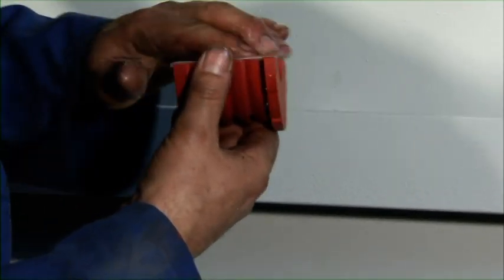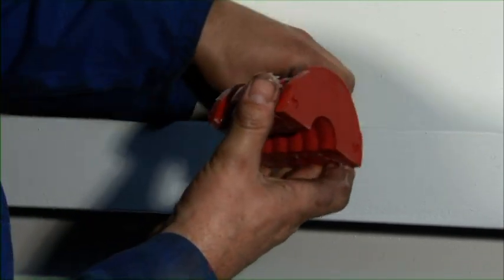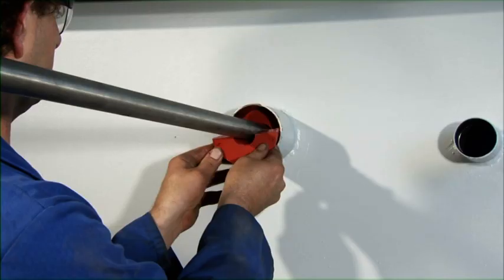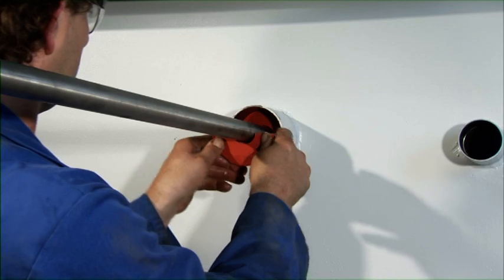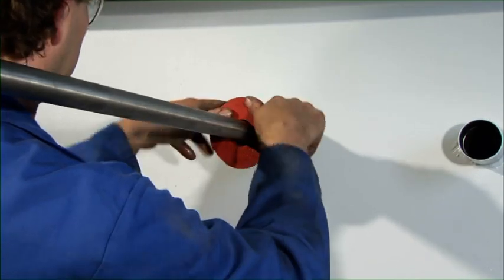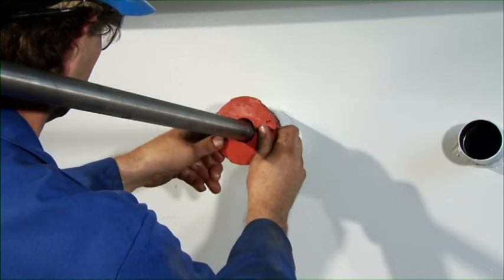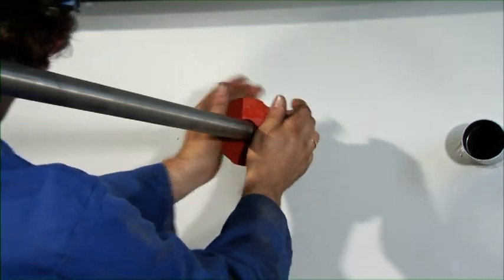Then both parts of the slip-sill plug are lubricated thoroughly on the inner and outer side, including the connecting surfaces. Both segments of the plug are placed around the ducted pipe. The plug is then pushed evenly, serration after serration, further into the conduit using a hammer and a piece of wood.